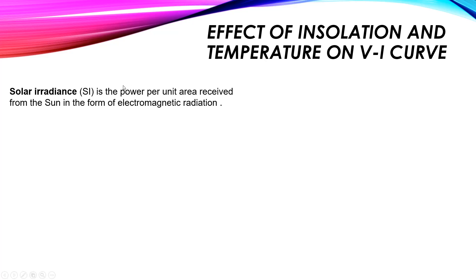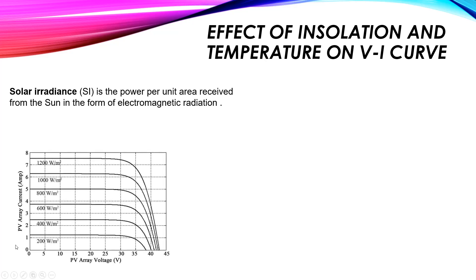It can also be expressed as energy per unit area — kilowatt-hours per meter squared. Now, here you can see the relation between the PV array current and the PV array voltage. At a solar irradiance of 200 watts per meter squared, the short-circuit current is nearly 1.2 amperes and the maximum voltage is nearly 38 volts.